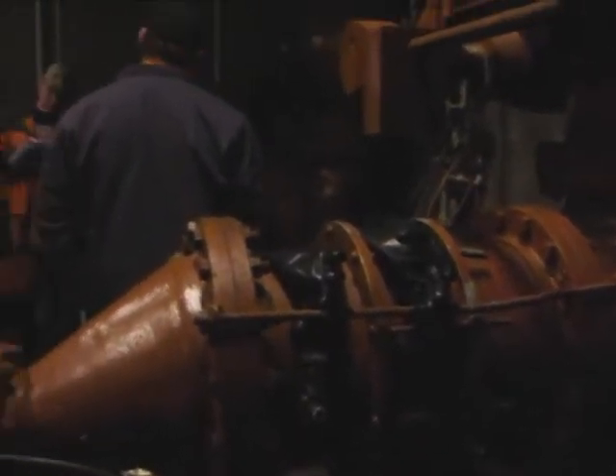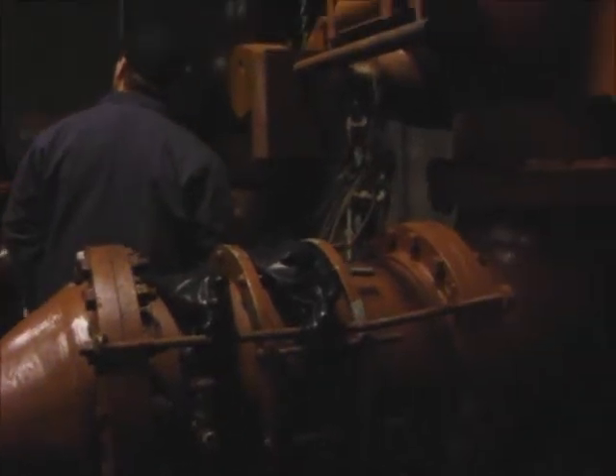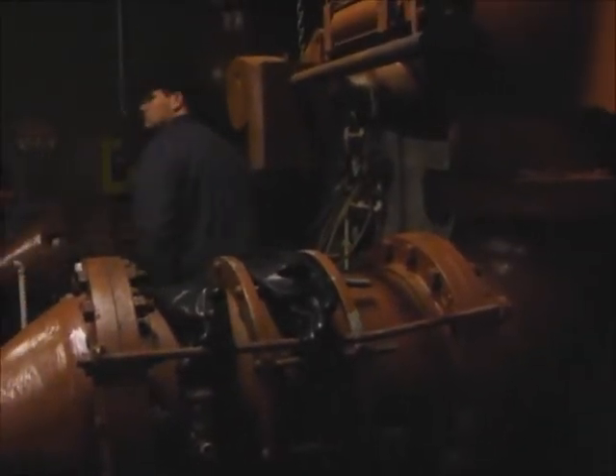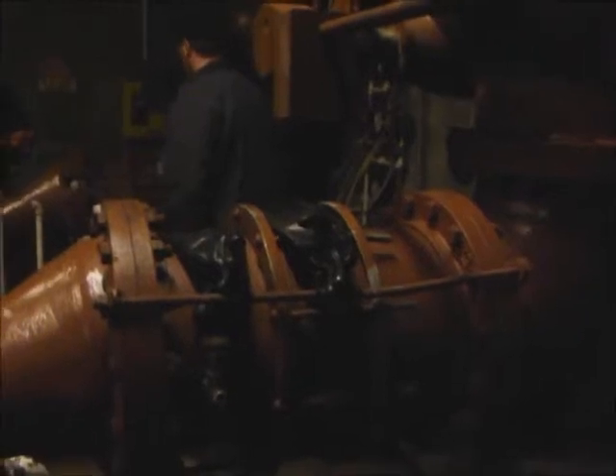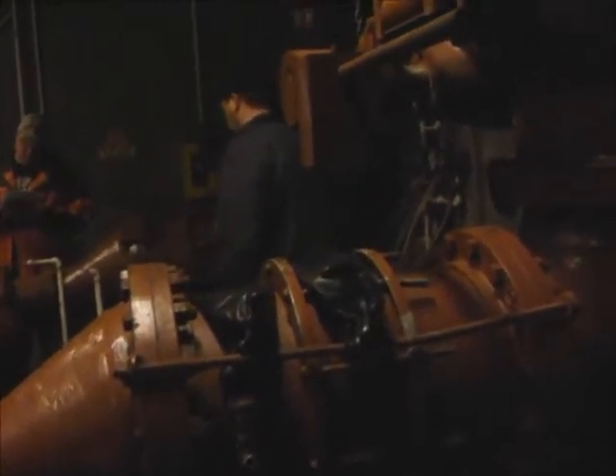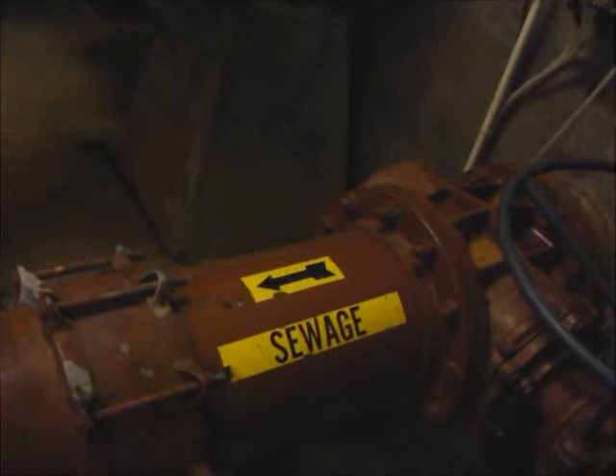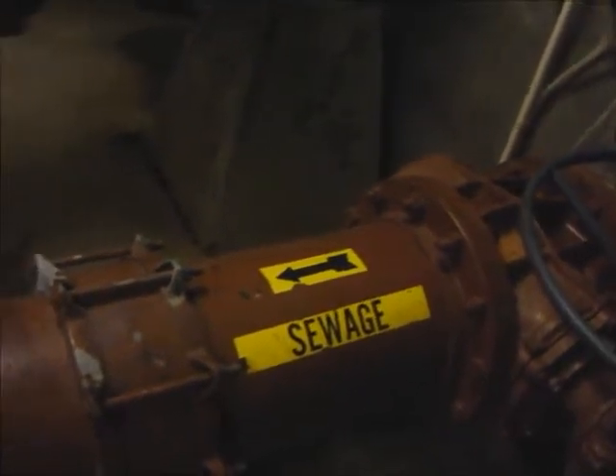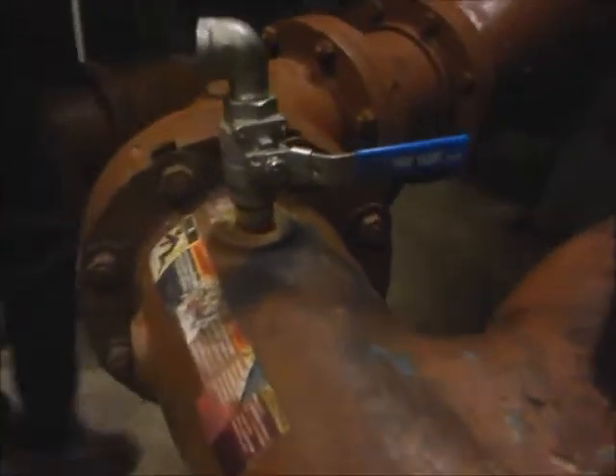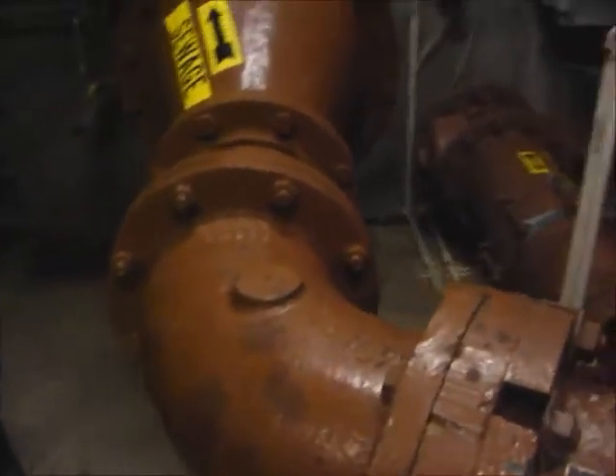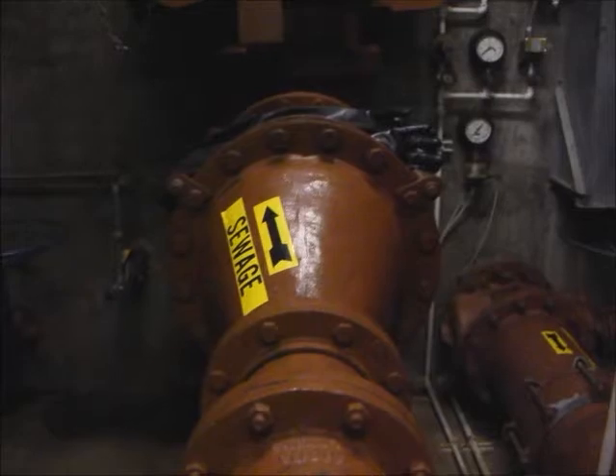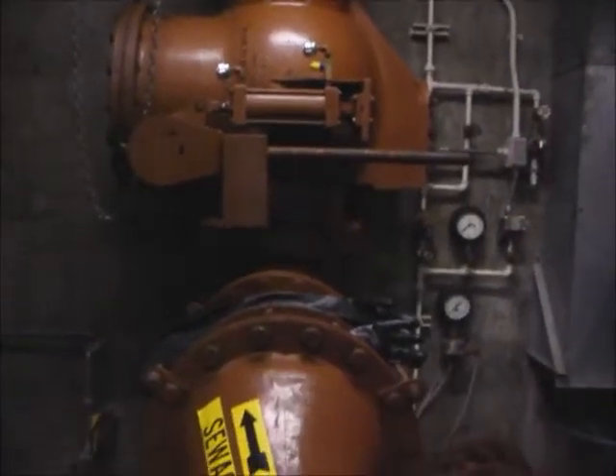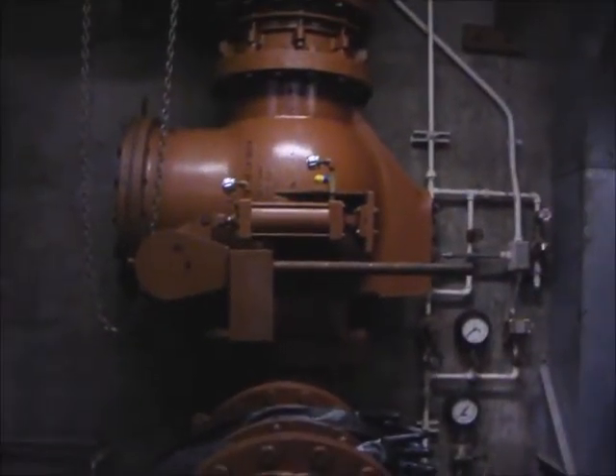This is your standard setup for a dry side in the old school way, with dry line pumps and centrifugal pumps. You got your suction, where the arrow says towards the pump, that's the suction side. It necks down to a 90 that goes up to the eye of the centrifugal pump and discharges out the side. It discharges to, I think it's a 16-inch or 18-inch force main that's up on top. Check valves are big old-fashioned plate pneumatic check valves.